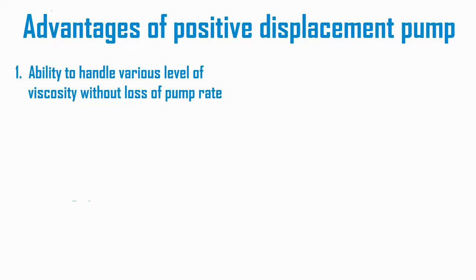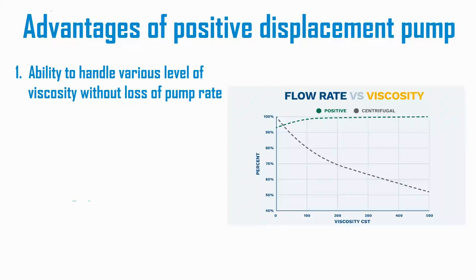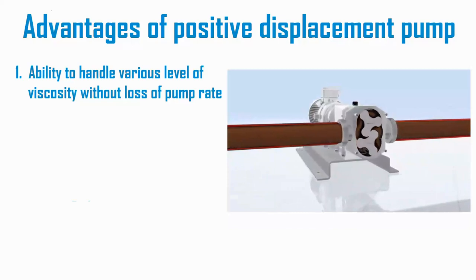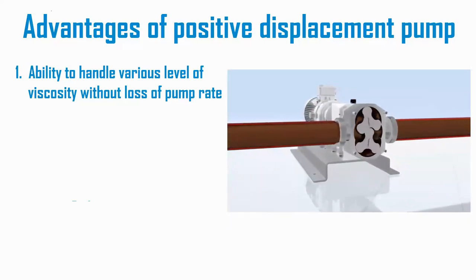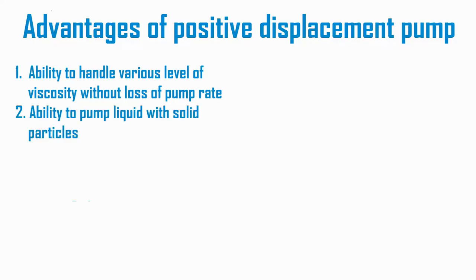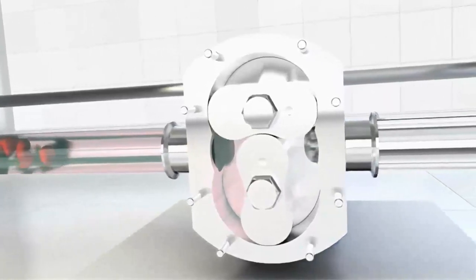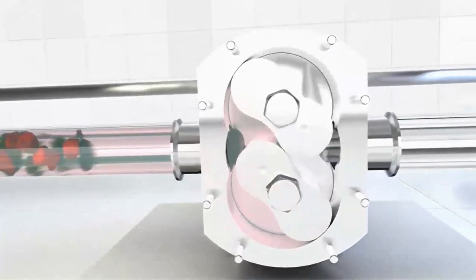The advantages of the rotary positive displacement pump compared to a dynamic pump or centrifugal pump: the rotary positive displacement pump is capable of pumping viscous liquids without decreasing the pump flow rate — for example, using a rotary lobe pump to pump chocolate liquid. It is also capable of pumping liquids filled with solids, such as a liquid filled with nuts, fruits, or other solid particles.